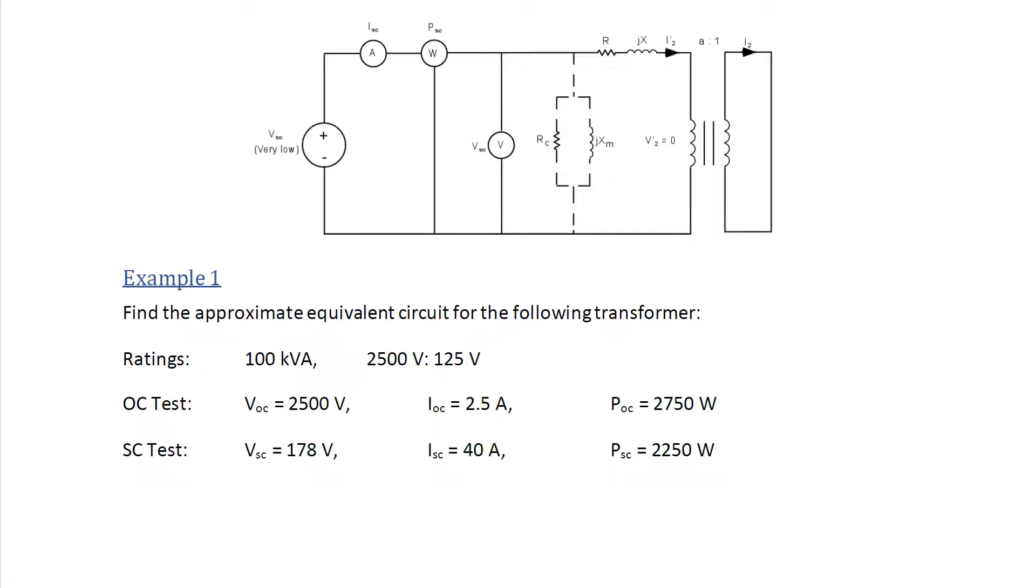Now let's try example one. Find the approximate equivalent circuit for the following transformer. The ratings are 100 kVA, 2500 volts to 125 volts. For the open circuit test, VOC equals 2500 volts, IOC equals 2.5 amps, POC equals 2750 watts. For the short circuit test, VSC equals 178 volts, ISC equals 40 amps, and PSC equals 2250 watts.